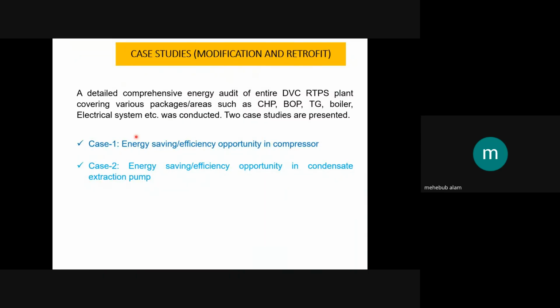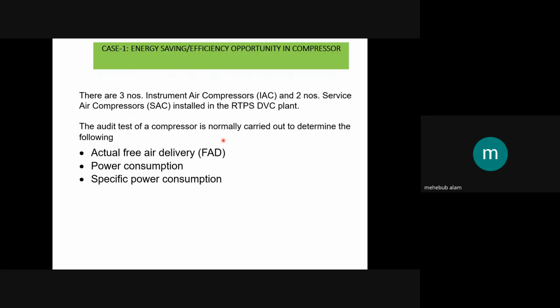A case study is shown here where an energy audit was conducted at the Damodar Valley Corporation Raghunathpur Thermal Power Station. The first case study is related to an energy saving opportunity in compressors. As told, there are two types of compressor. The first is the instrument air compressor, and the second is the service air compressor. The instrument air compressor is required to operate the pneumatic valves, while the service air compressor is required basically for cleaning purposes. During an energy audit, the FAD test, actual free air delivery test, and specific power consumption of each compressor were done.